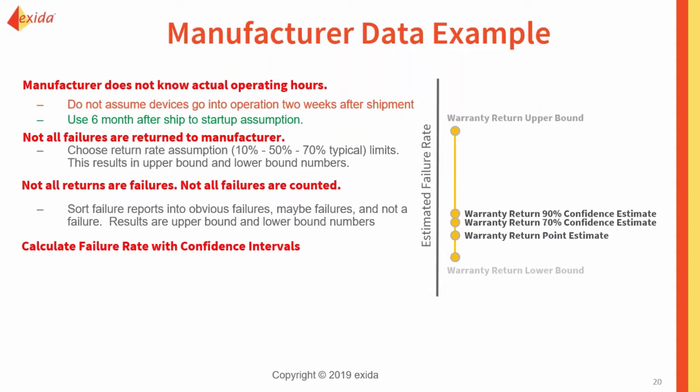We've seen a lot of field failure studies that assume that the device goes into operation immediately or a week or 2 weeks after shipment. And that's going to be very optimistic. When we do field failure studies, we use at least 6 months after shipment to start up as our built-in assumption. Next, we're going to look at how not all failures are returned to the manufacturer.